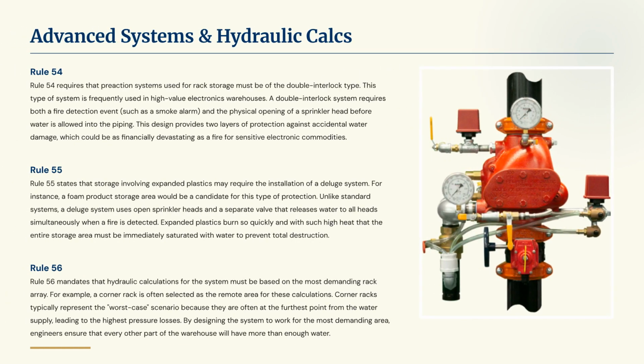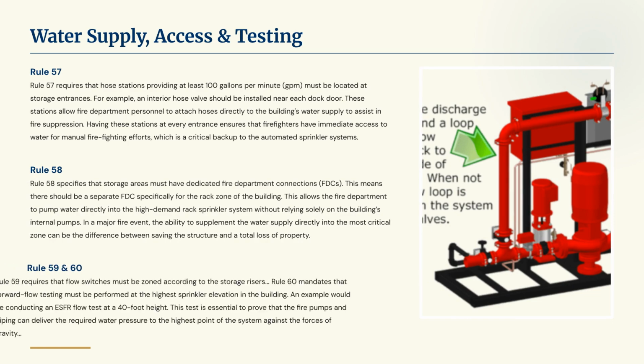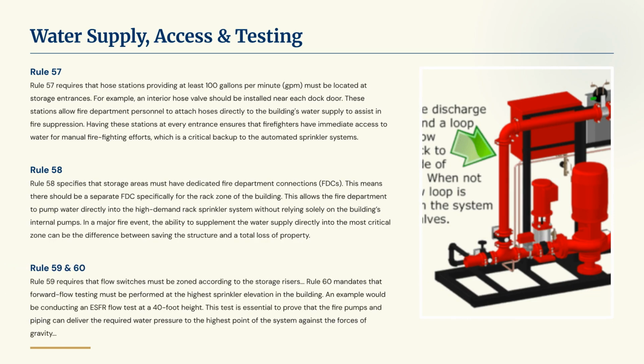Rule 54 mandates double interlock pre-action systems for rack storage. Rule 55 specifies deluge systems for storage involving expanded plastics. Rule 56 requires hydraulic calculations to be based on the most demanding rack array. Rule 57 requires hose stations providing at least 100 GPM at storage entrances.